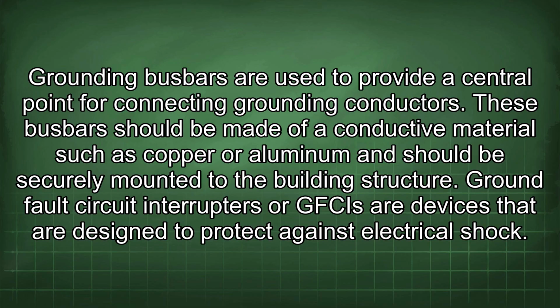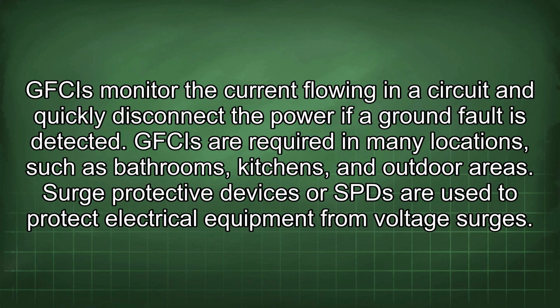Grounding busbars are used to provide a central point for connecting grounding conductors. These busbars should be made of a conductive material such as copper or aluminum and should be securely mounted to the building structure. Ground fault circuit interrupters, or GFCIs, are devices that are designed to protect against electrical shock. GFCIs monitor the current flowing in a circuit and quickly disconnect the power if a ground fault is detected. GFCIs are required in many locations, such as bathrooms, kitchens, and outdoor areas.